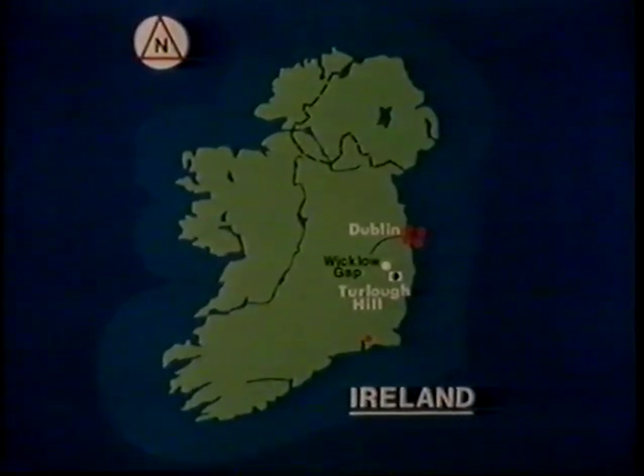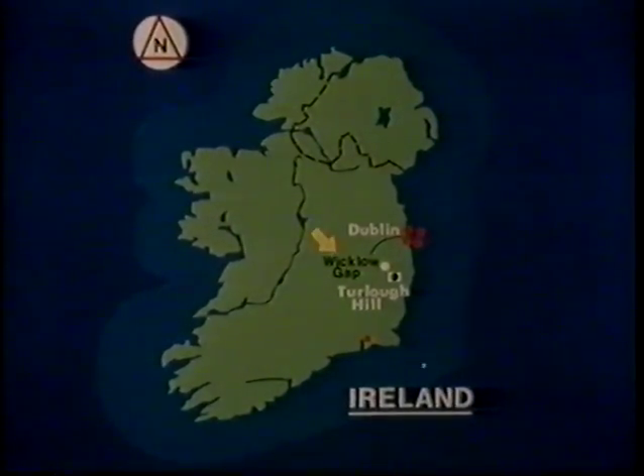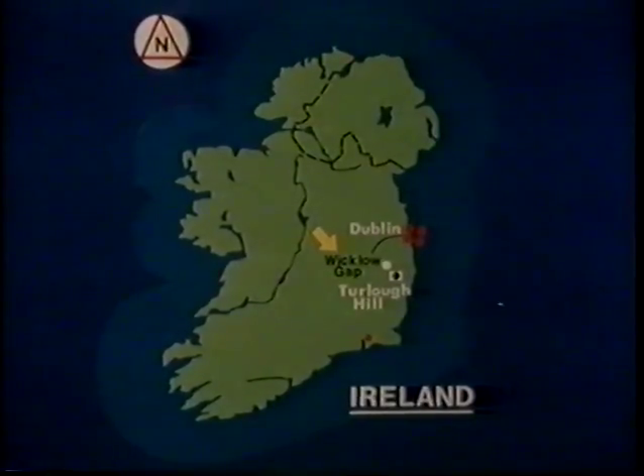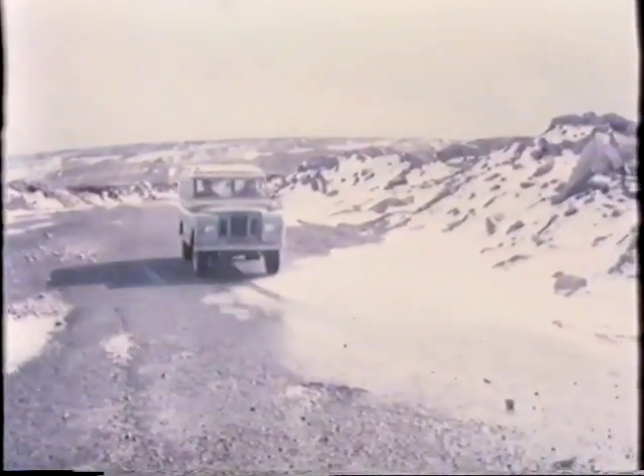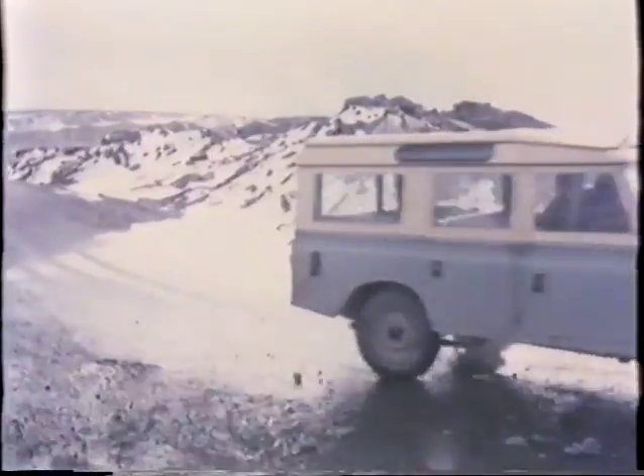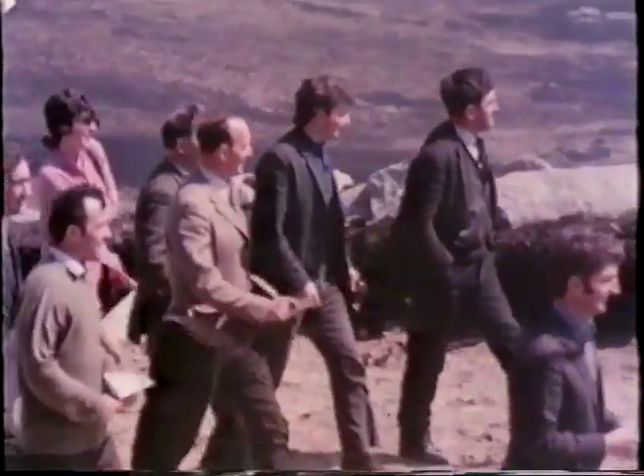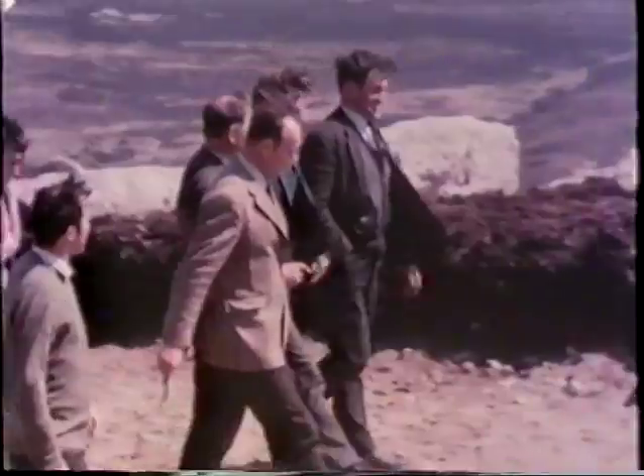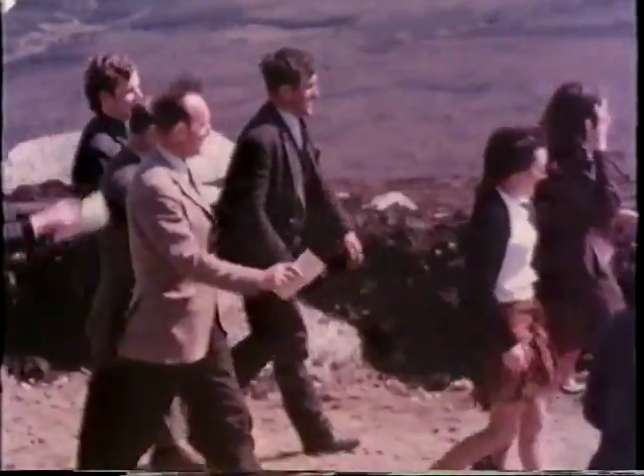The Turlough Hill site had another advantage in being close to Dublin, a major centre of load demand, and close to the East Coast thermal stations. But there were disadvantages too. The height above sea level, almost 700 metres, meant the risk of costly delays due to the weather. And the position of the site in a high amenity area involved heavy expenditure for environmental reasons.